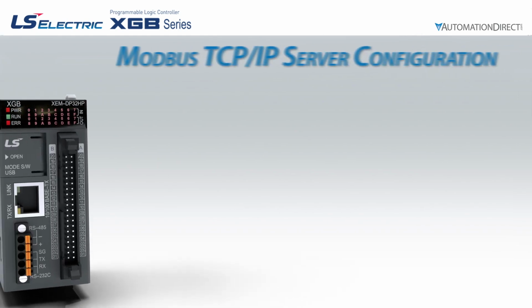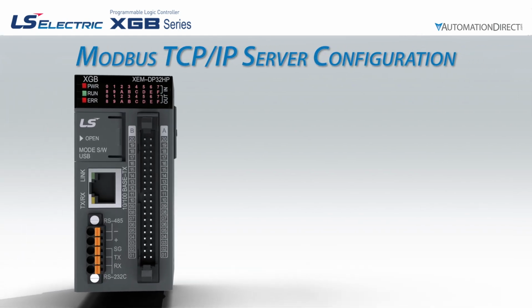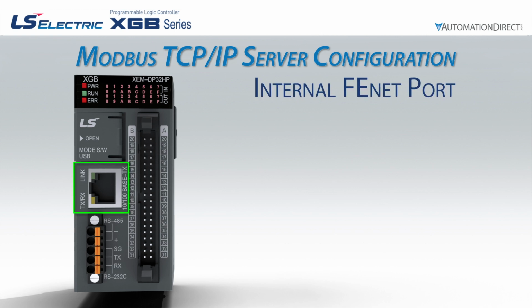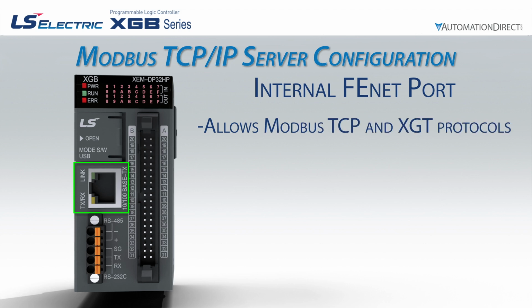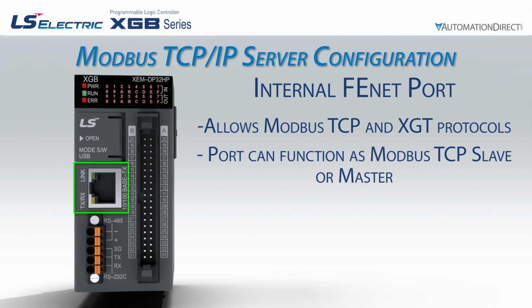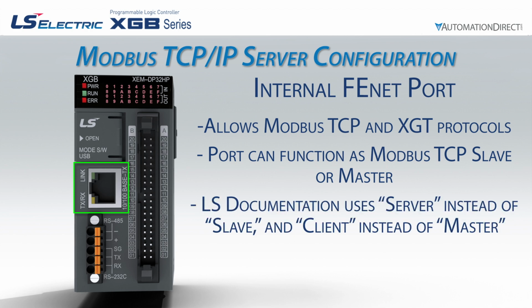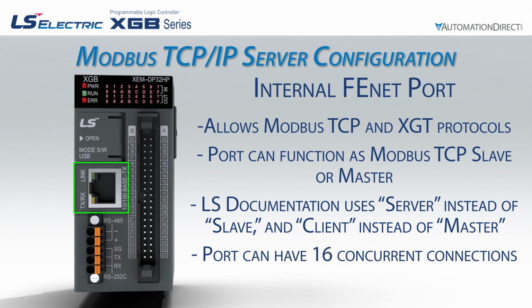The XGB PLC offers many ways to communicate over Ethernet. The onboard Ethernet port is referred to as the internal FENet and allows Modbus TCP and XGT protocols. For the Modbus TCP, the PLC allows configuration as both a Modbus slave and master. In LS documentation, Modbus slave is also called Modbus server, and Modbus master is also called Modbus client. The Modbus server and client functions for the XGB PLC can share up to 16 concurrent connections.